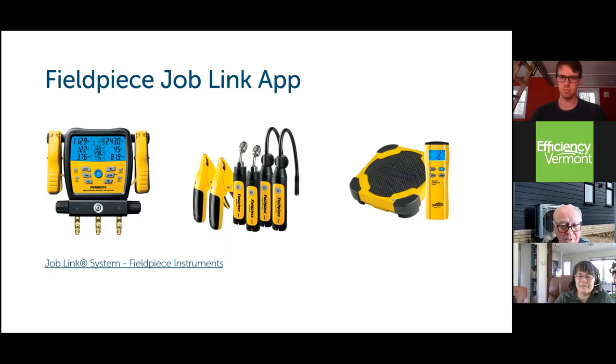Non-invasive service would take a sensor like that, and you could hook it onto your valves, especially on conventional, but even more so on ductless splits, because the charge is so critical. We don't always want to put a manifold set on a system. That's the first thing we always did in the past. It should be the last thing we're thinking about today, because when you put a manifold set on there, you're going to lose refrigerant, and you can contaminate the refrigerant with just that manifold set.